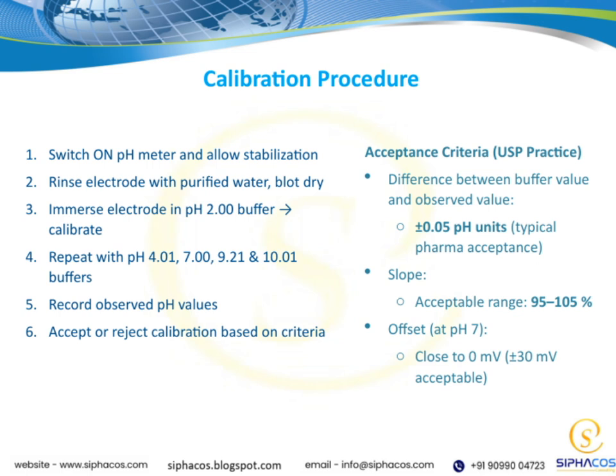Next, we rinse the electrode with purified water and blot it dry to remove any contaminants. We then immerse the electrode in a pH 2 buffer to calibrate, followed by repeating the process with buffers at pH 4.01, 7, 9.21, and 10.01. It's important to record the observed pH values at each step carefully. Finally, based on these recorded values, we decide to accept or reject the calibration, making sure they meet the established criteria. These steps are vital to ensure our pH measurements are precise and reliable for our pharmaceutical processes.